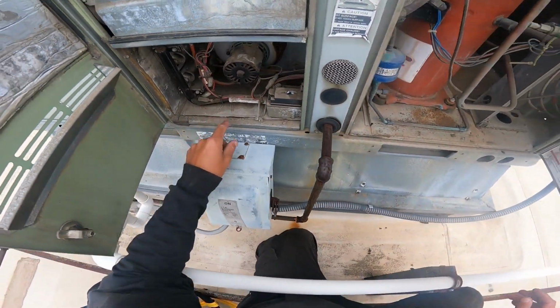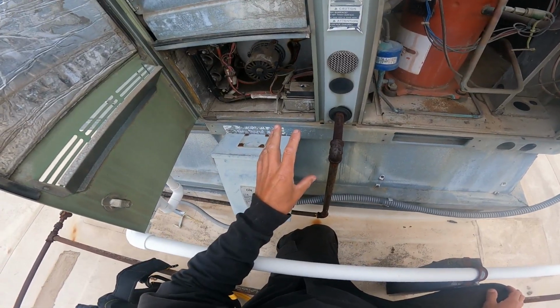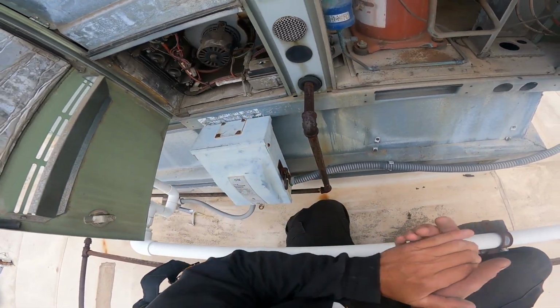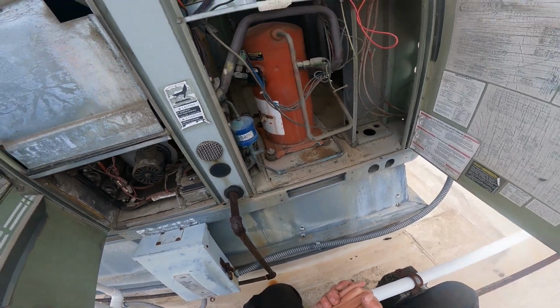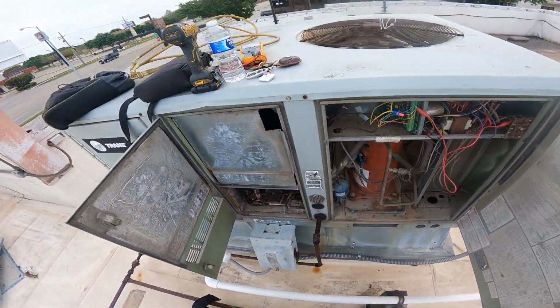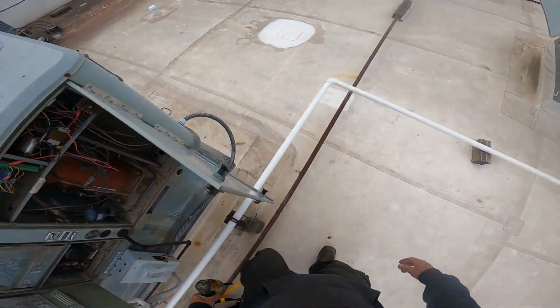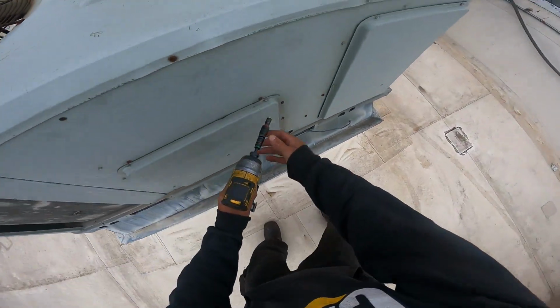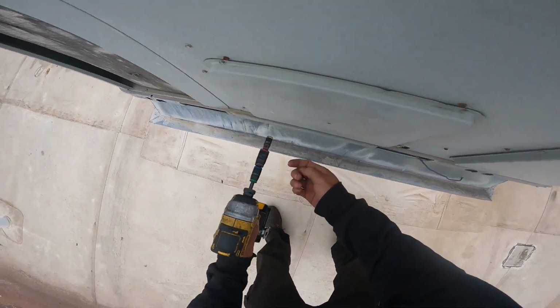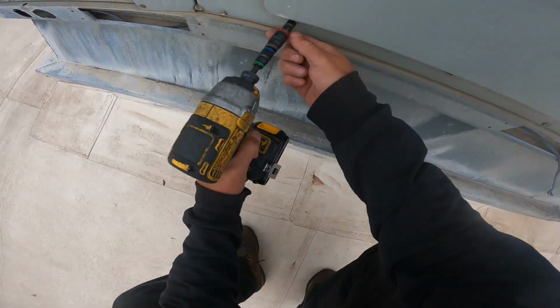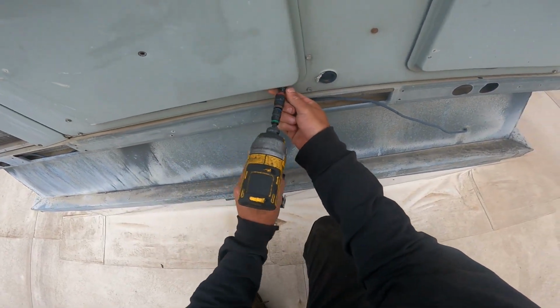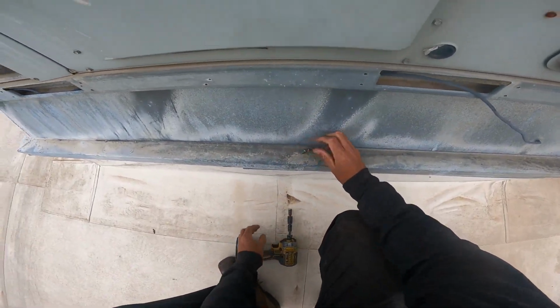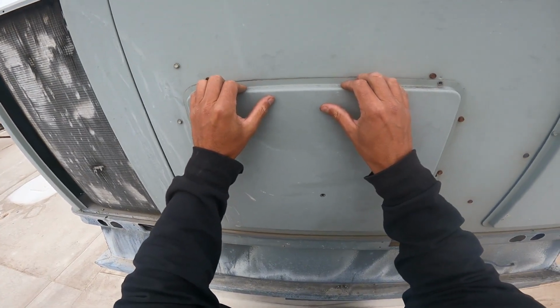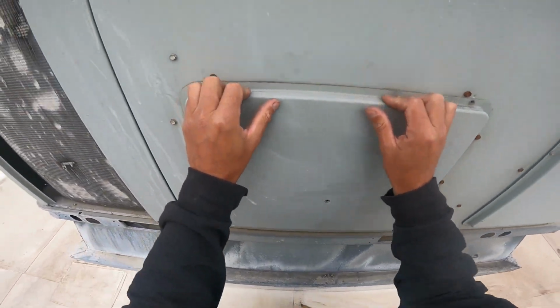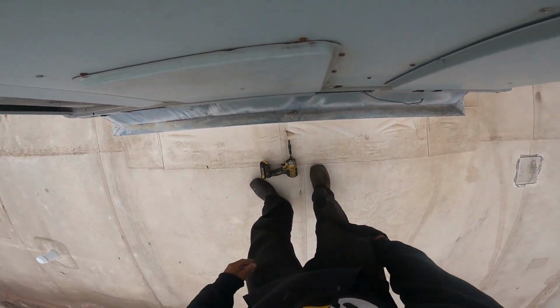I don't really care about heat. This thing is trash. All right, this unit is trash. It's a Trane, so I don't know how the heat exchanger is going to look, but if I can rule out that, then I've got one more step towards telling them that this is not going to be repairable. With the age of it, there's a very good chance the heat exchanger is bad, especially since it's never even been checked, because I can't pull the panel off.